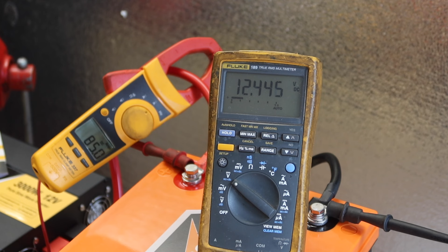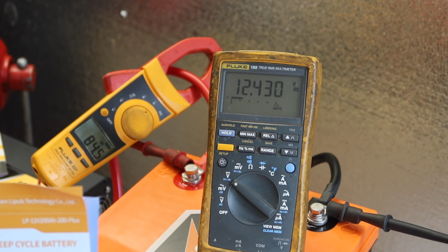The battery says it can do 200 amps, so I'm only at half its capacity or less. Knowing the battery wasn't fully charged, it claims its nominal voltage is 12.8, but it's supposed to charge at 14.6 volts, and will shut itself off once it reaches below 10 volts. I've heard that when you charge these batteries up, the resting voltage will be around 13.6. Literally, I just took it out of the box and it had enough charge to run a heater that is cooking my leg right now.